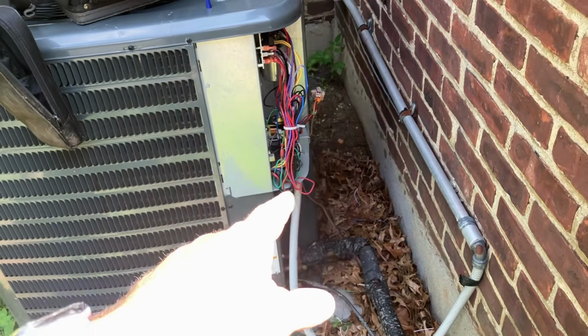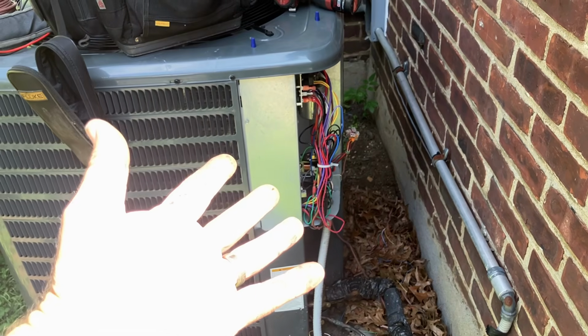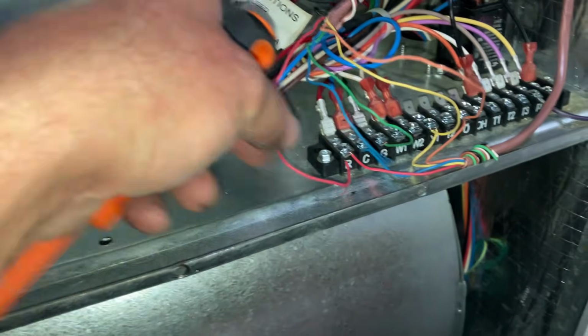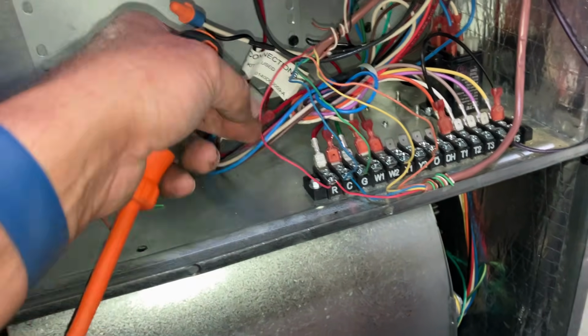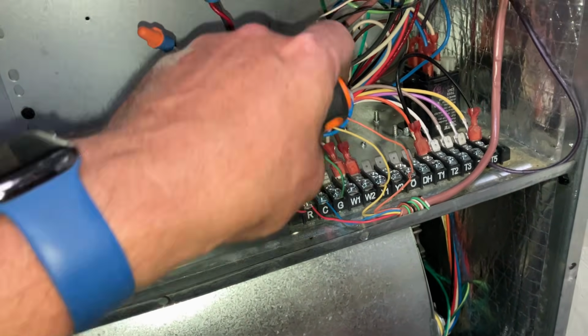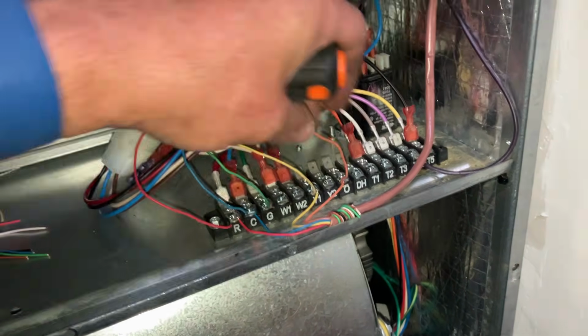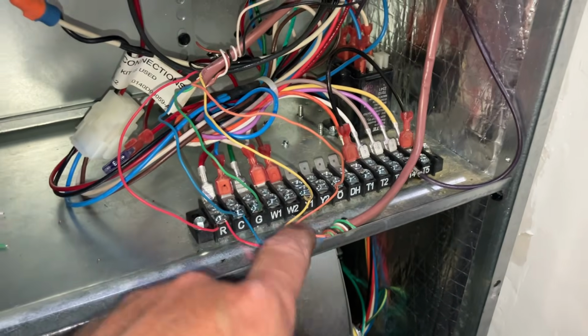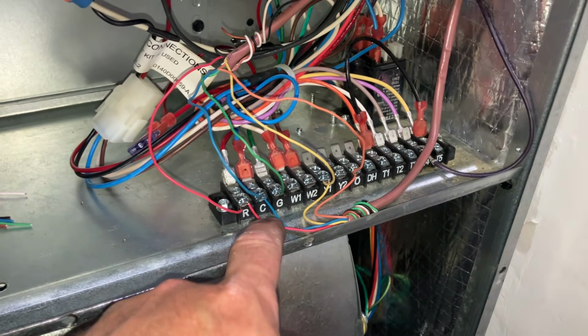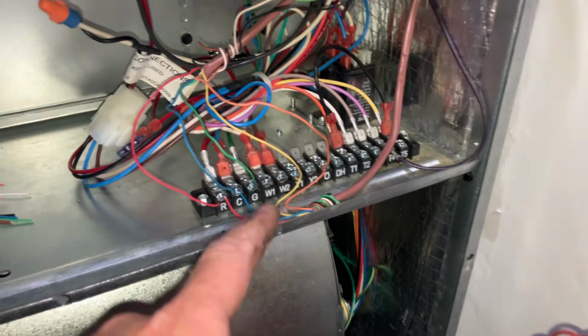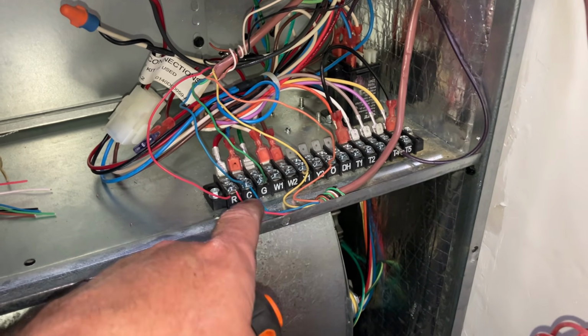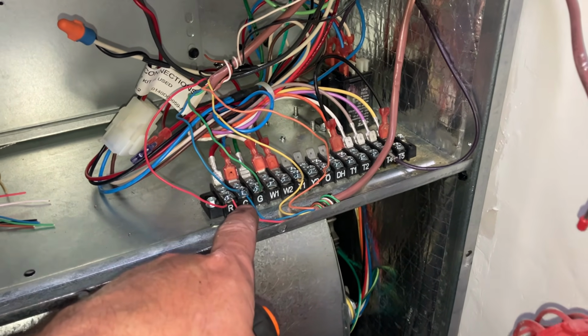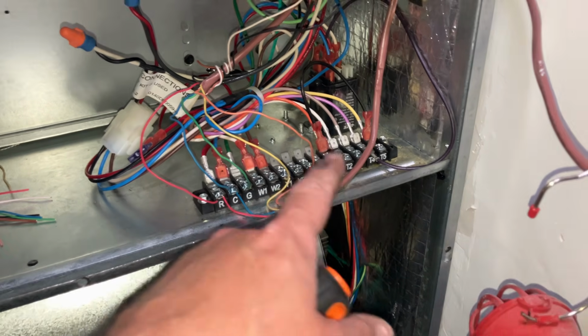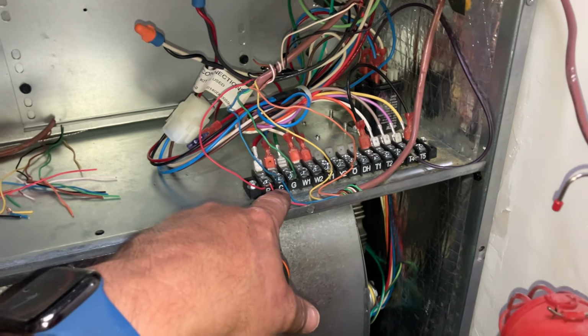Let's connect the wiring at the air handler and hope she works. All right, these are at the thermostat: R, common, fan, Y, OB, and this is coming from my condensing unit. They're all tight. I'm triple checking this because the C wire was basically broken off, and the R and C, when I first got here, weren't even in position. They were just hanging out there.